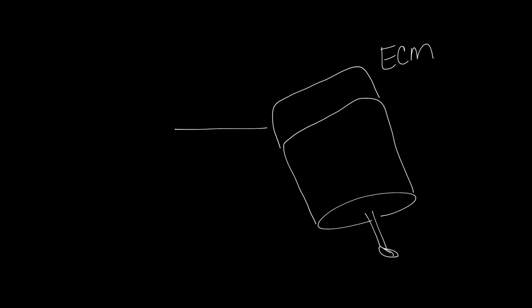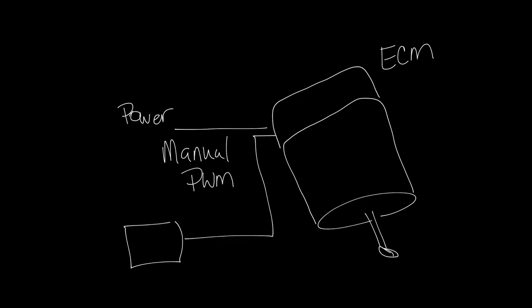The newer electronically commutated motors, or ECMs, are very different from PSC motors. ECMs are smart motors that can be programmed to provide pressure-independent volume control, or they can be programmed to provide constant torque. Pressure-independent control allows the motor to automatically increase or decrease its speed to compensate for changes in external pressure. Constant torque control causes the motor to behave more like a traditional fan motor and eliminates any control stability issues when operating at very low speeds.